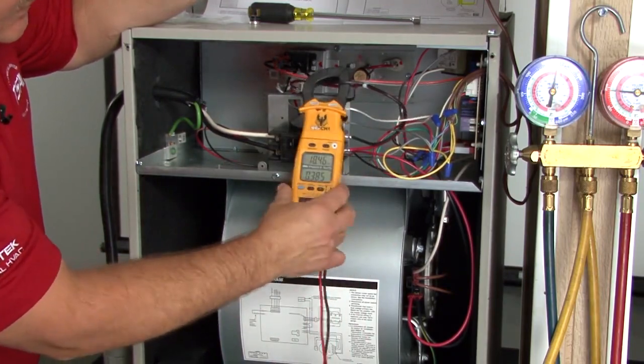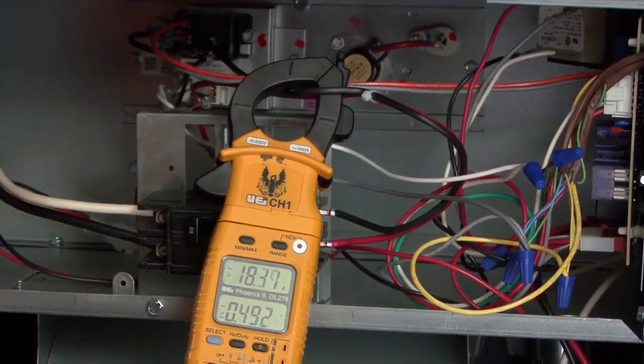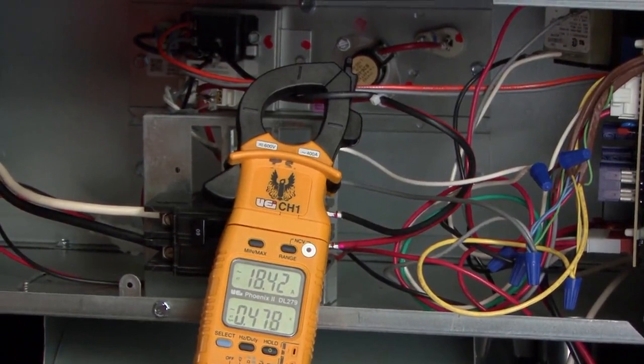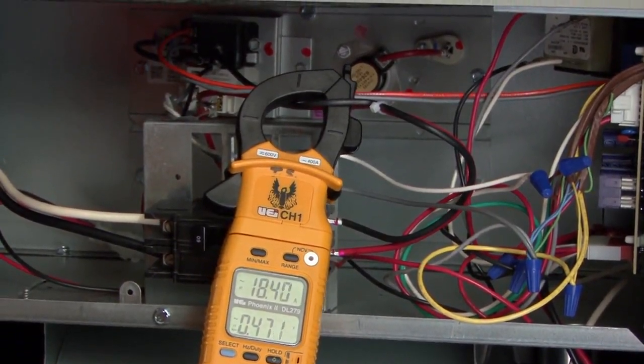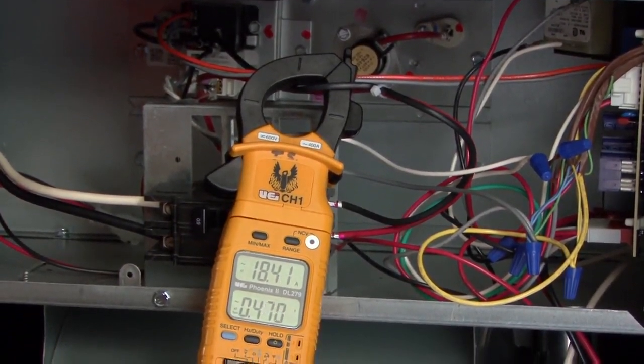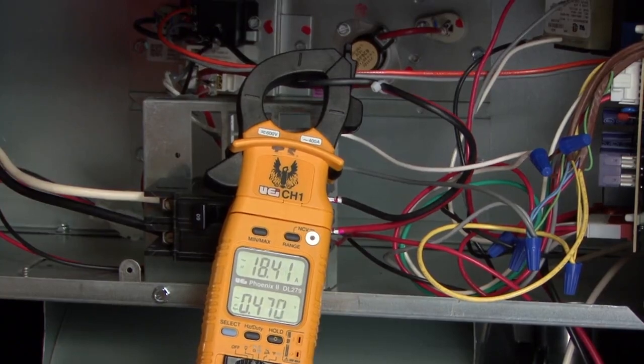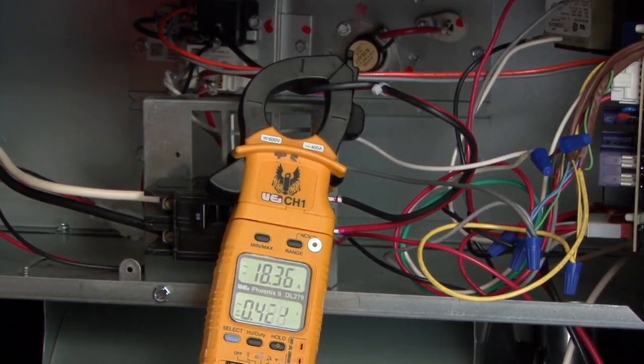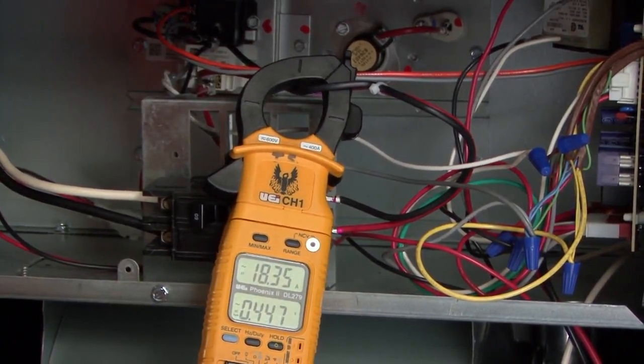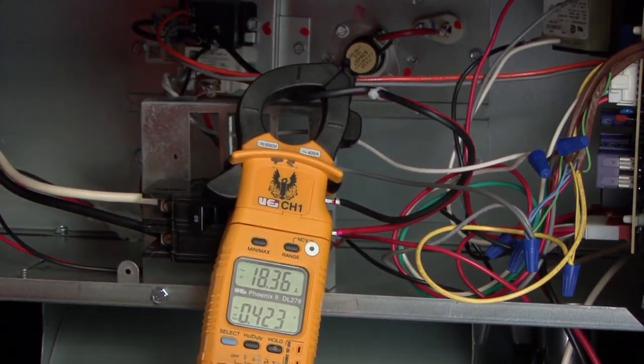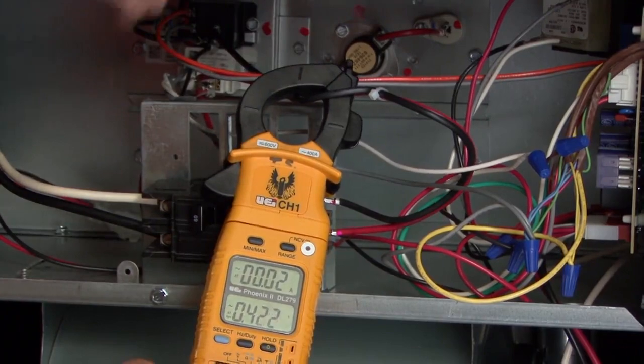So you can see here, we're still around 18 amps. We just don't have the blower included anymore. We're only testing the electric heat of the element. So two things you want to do here: make sure all the electric heat elements, however many are in there, are all cycling on. And then the second thing you want to do is turn the thermostat down and make sure it cycles off completely.